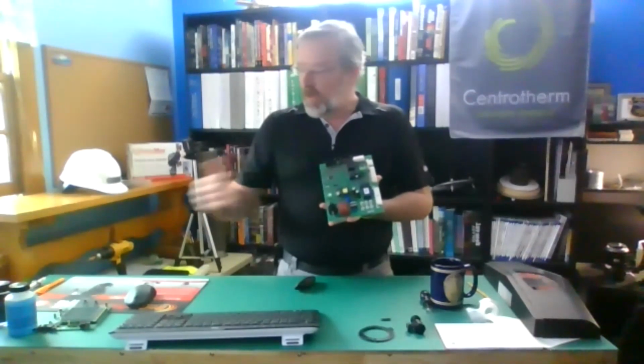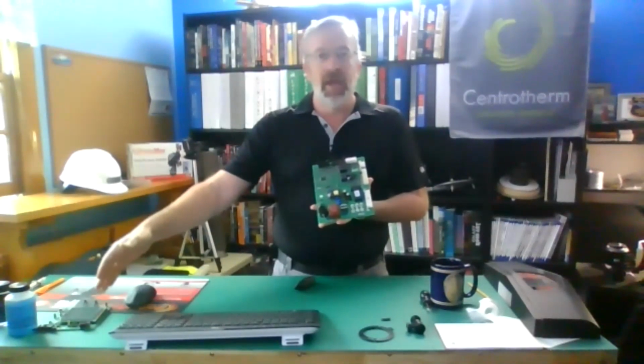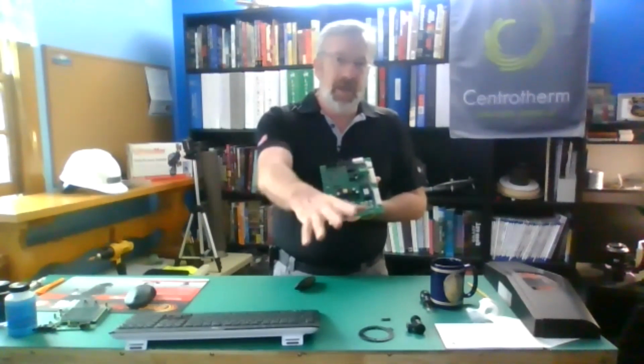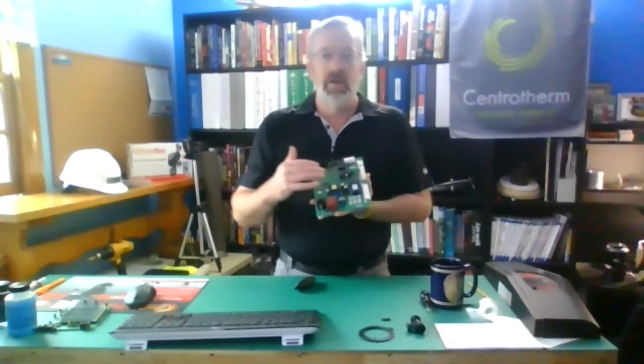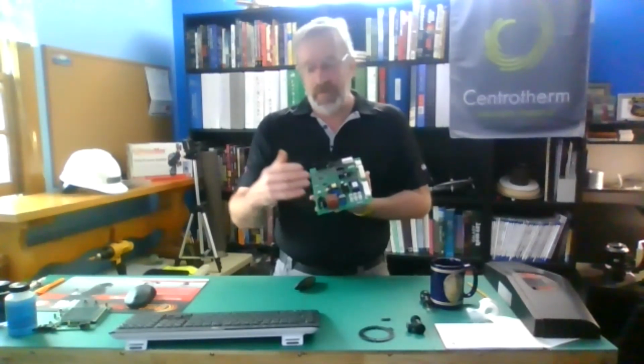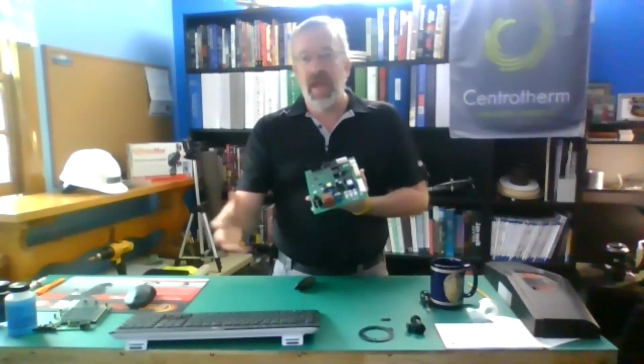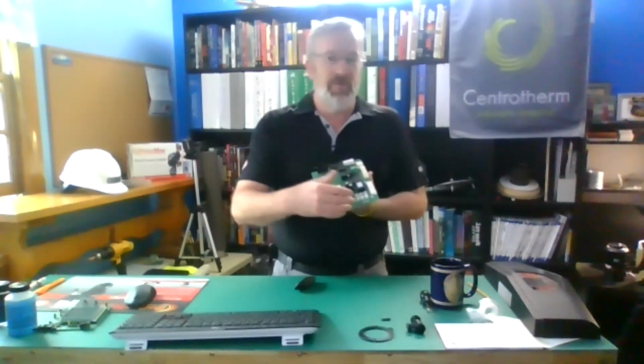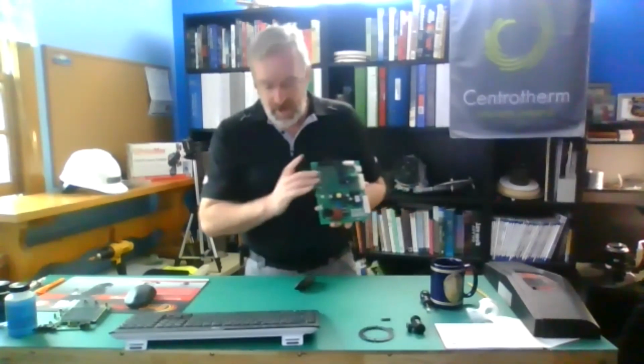The main control board connects to the display interface. And then basically from here, everything goes out to the boiler. We connect to all the sensors, we connect to the fan, we connect to the gas valve, we get to 24 volts, we do everything like that. So that's really, this is where everything resides on board here.